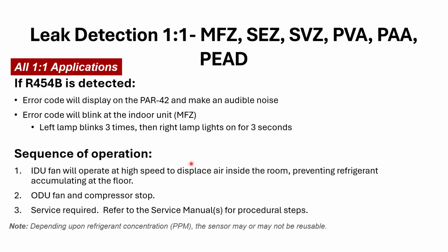So sequence of operation, indoor unit fan will operate at high speed to displace the air inside the room, preventing refrigerant accumulating at the floor. Outdoor fan and compressor stop. Service required, refer to service manual for the procedural steps after that. I think we might have some of that in here too. It steps you through the process when something's detected and what's happened and when to power the unit off also.